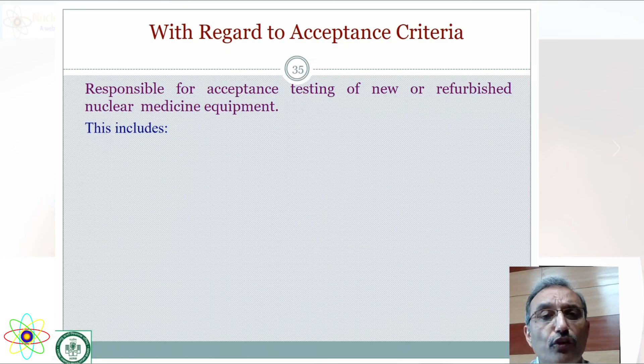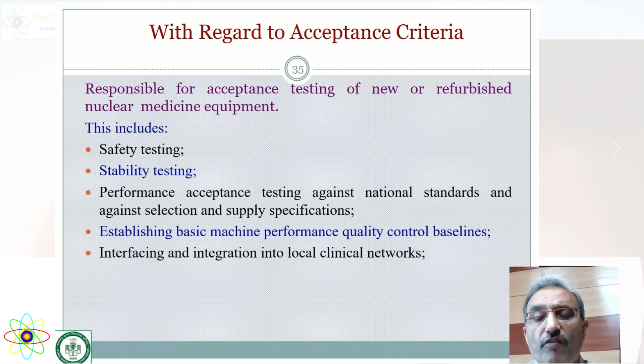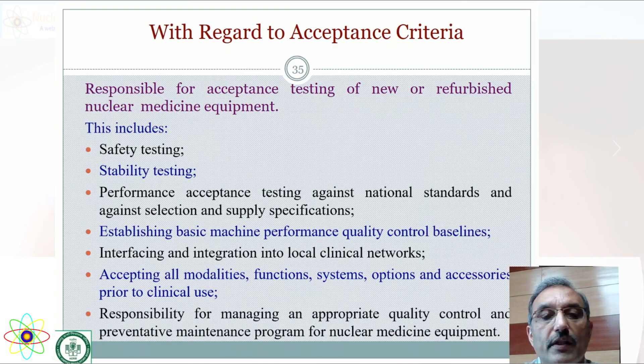They need to have reference values so that as and when the periodic QA is carried out, they can compare whether the equipment is meeting those reference values or not. Apart from that, there are tolerance limits assigned or given by the regulatory authority. Accepting all modalities, functions, systems, options, accessories prior to clinical use. Again, a very important role which they are supposed to play, and they are playing too.